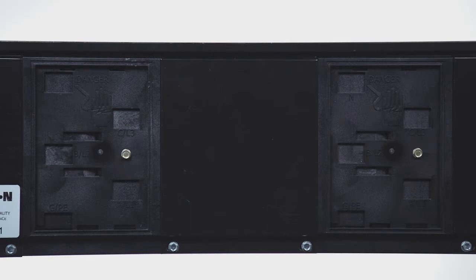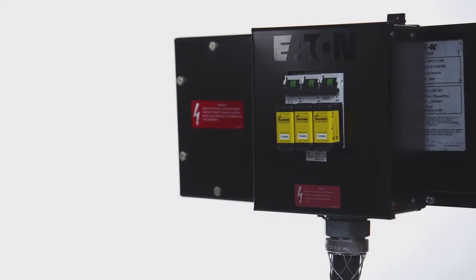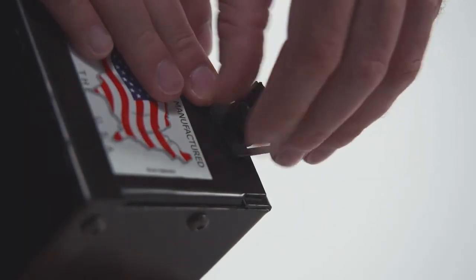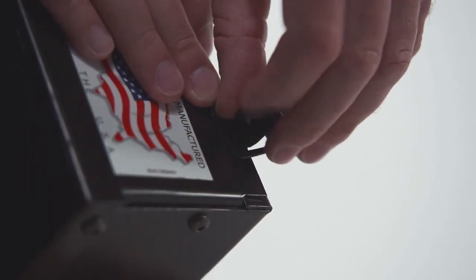The plug-in bus sections are equipped with a plug-in opening along the bus every 12 inches. A bus plug can be installed in any or every one of these outlets. To install the plug, first remove the safety shutter screw from the shutter assembly. Next, loosen the bolts on the clamp and guide assembly.